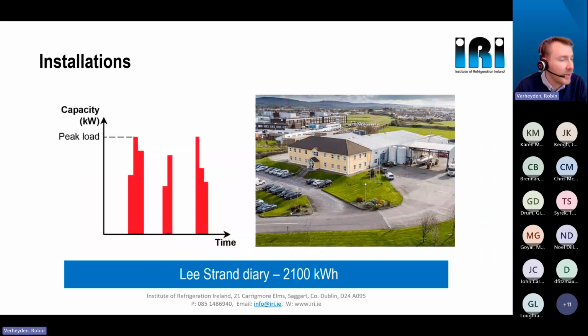A totally different installation is, for example, a dairy. Here you can see the load profile. It's a pasteurization process, meaning the milk needs to be cooled down very quickly, resulting in high peaks and very short melt times. Here, external melt is selected instead of internal, because the direct contact of water and ice gives temperatures close to 1 degree, allowing the ice block to melt down very quickly, very fast.